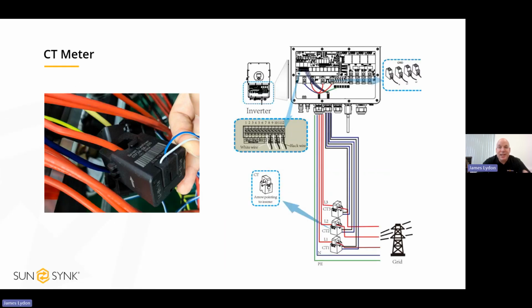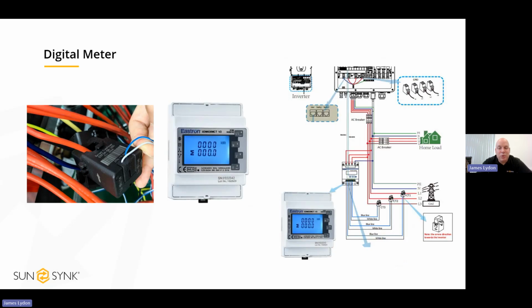This is the standard CT. So again, with the single phase inverters, you get one CT in the box as standard. Obviously, with three phase, you'd get three. And they would all connect inside the inverter. There's a terminal strip that your CTs will connect into. This is showing you the Eastron meters. So if you are using the Eastron meters, they will connect back to our inverter on a full patch lead.